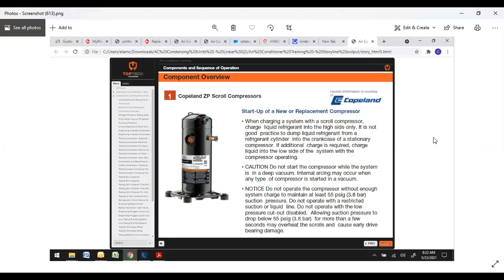Startup of a new or replacement compressor. When charging a system with a scroll compressor, charge liquid into the high side only. It is not a good practice to dump liquid refrigerant from a refrigerant cylinder into the crankcase of a stationary compressor. If additional charge is required, charge liquid slowly into the low side of the operating system. Do not start the compressor while in a deep vacuum. Internal arcing could occur.